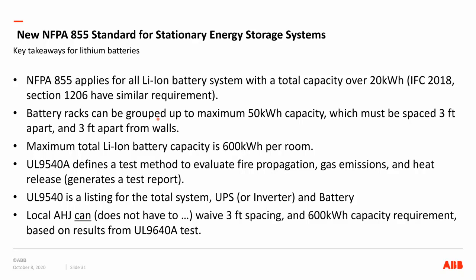But for 855, the requirement with a lithium ion battery is that it applies to anything over 20 kilowatt hours. Groups of batteries or battery cabinets over 50 kilowatt hours have to be separated from each other and from walls by 3 feet. And there's a requirement that they will not allow more than a total capacity of 600 kilowatt hours in one room.